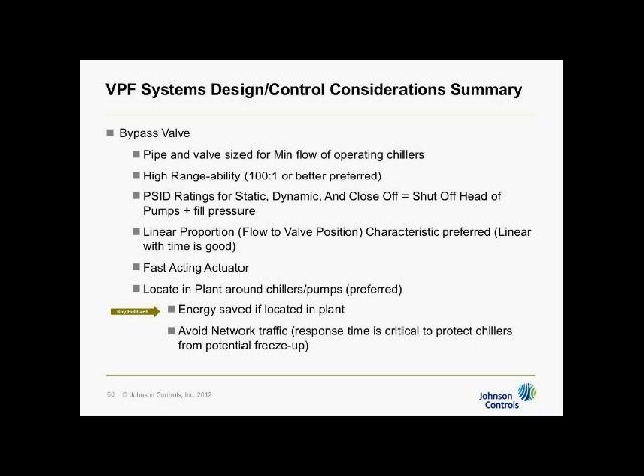It doesn't matter for the function of it where it's located. It can be at the end of the system, it can be at the beginning, right in the plant. And it'll function as long as you have it direct wired. We usually recommend that it's put in the plant, one, because direct wiring is easy, and two, I get the amount of the time that I need, and I save energy.